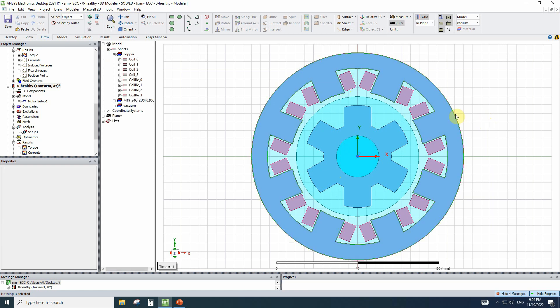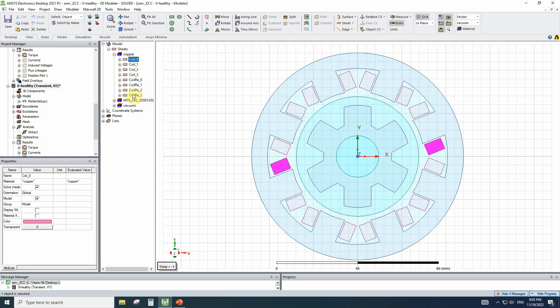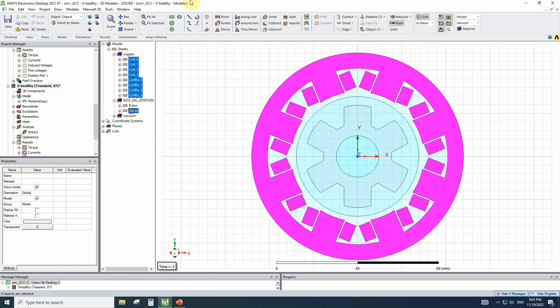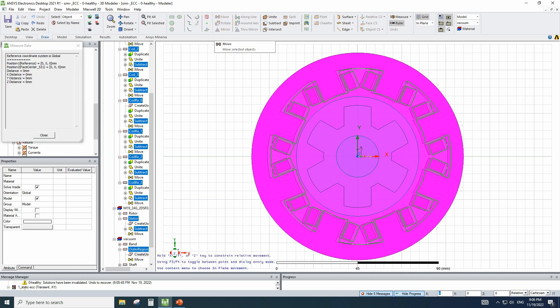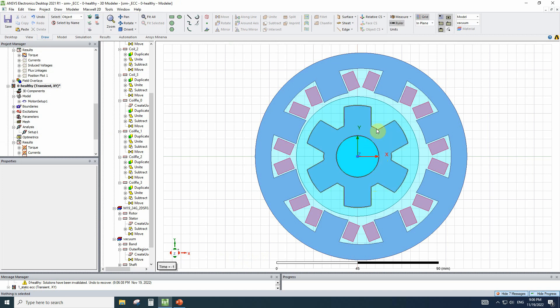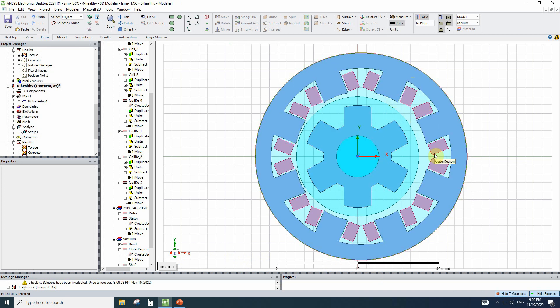Now I will select all the stator parts and all the windings, and move all of them, for example, 2 millimeters. Now the center of the rotation is not equal to the center of the band and center of the rotor, but the whole stator moved. In this case, the air gap is fixed — it's not uniform, but fixed.